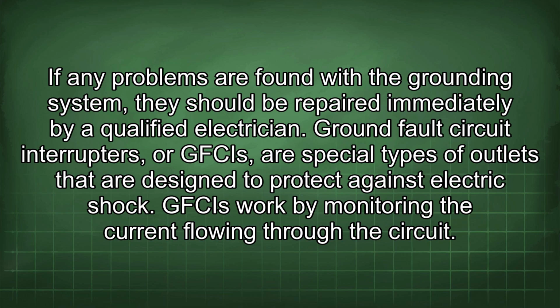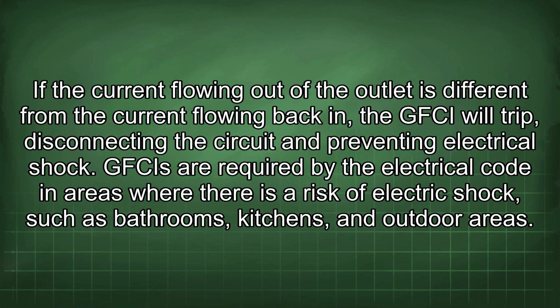Ground fault circuit interrupters, or GFCIs, are special types of outlets that are designed to protect against electric shock. GFCIs work by monitoring the current flowing through the circuit. If the current flowing out of the outlet is different from the current flowing back in, the GFCI will trip, disconnecting the circuit and preventing electrical shock.